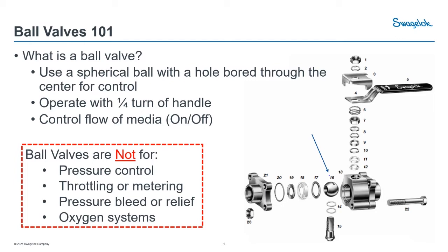Also avoid ball valves in oxygen systems. That fast shutoff with oxygen can cause fast adiabatic compression, which heats up your oxygen system. If you have anything potentially combustible, you can start a chain reaction fire. We try to avoid ball valves and instead go for a multi-turn needle valve so shutoff happens slowly and tempers that reaction. The biggest thing is to avoid any sort of throttling — ball valves should be full open or full closed at all times. Partial opening causes seat erosion and your valve will start leaking by.